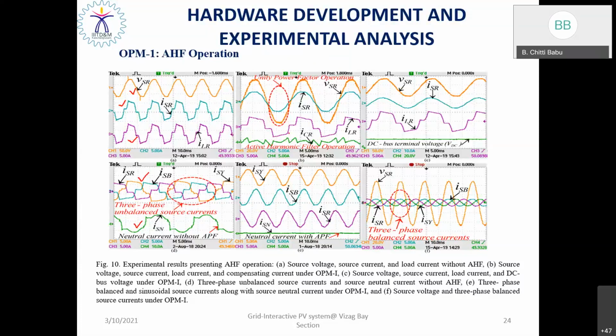With the help of this active harmonic filtering operation of the inverter with the suitable control, your supply current, or the grid current waveform, becomes sinusoidal, and moreover it is in phase with the supply voltage, and again there is a possibility of unity power factor operation. See the corresponding compensating current that has been injected by the inverter in order to compensate the harmonic current present in the grid current due to the non-linear unbalanced load connected at the point of common coupling. You can see all 3-phase supply currents become sinusoidal. Moreover, the neutral current is well compensated. There is no neutral current. Obviously, the zero sequence component is absent here as we use the 4-leg inverter.